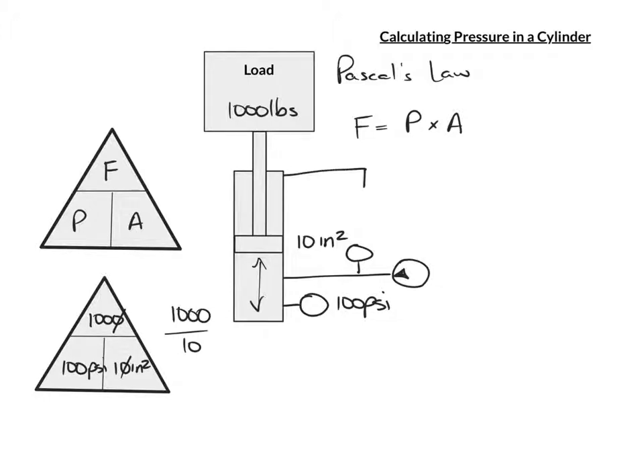And the outlet of the cylinder would have to go to a reservoir so that we can allow for flow. But we would have to overcome the 100 psi requirement of the load for the cylinder to move. If we were at 100 psi, we would simply hold the load.